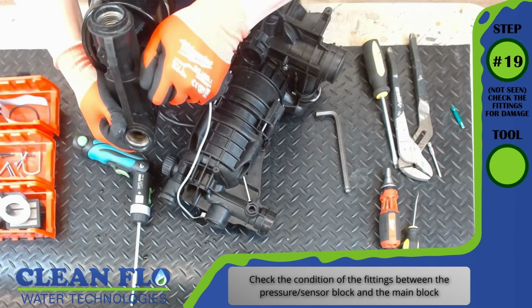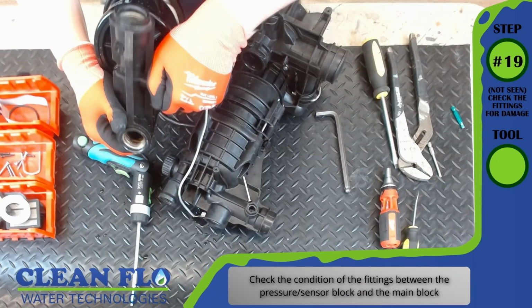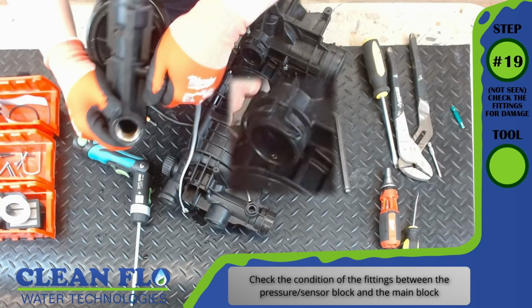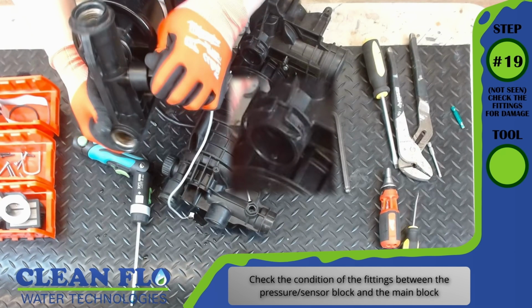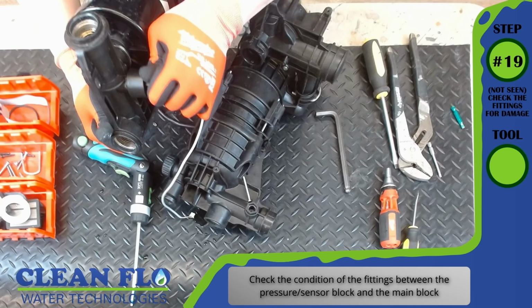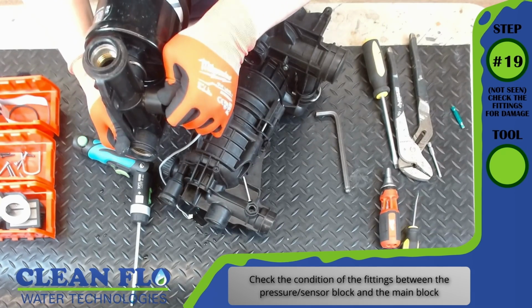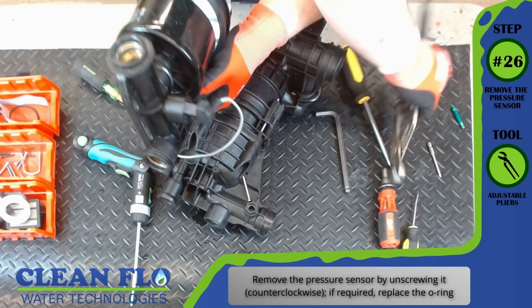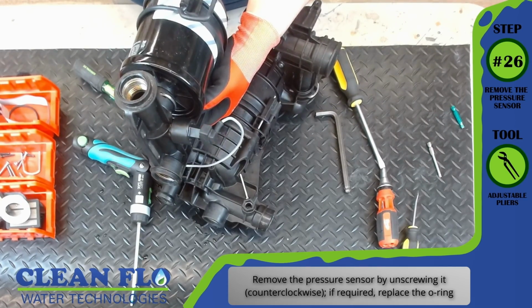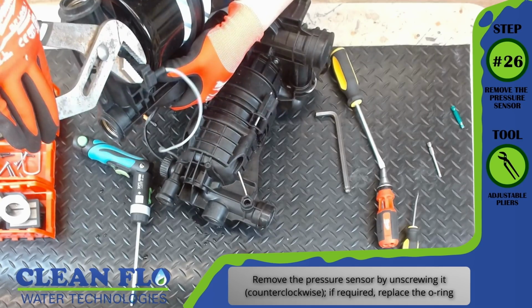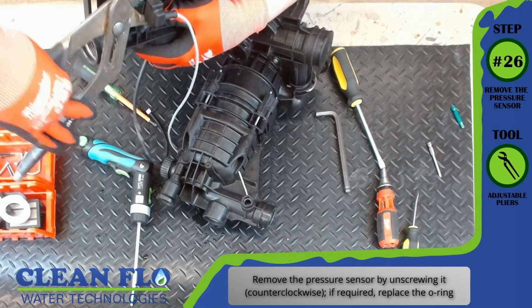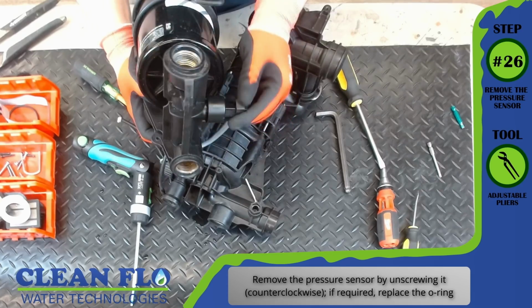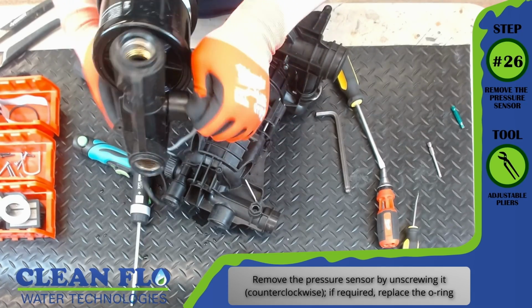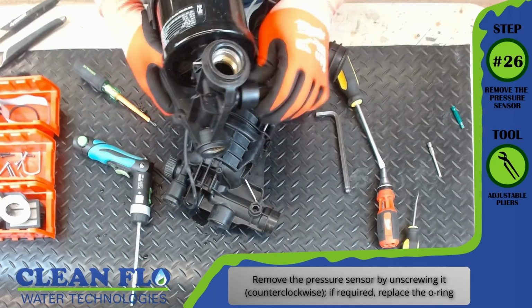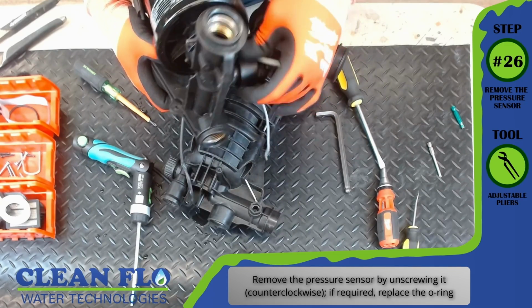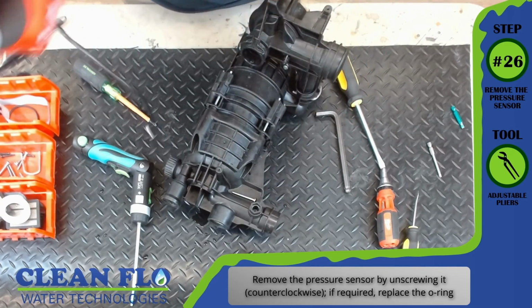Step 19, not seen. Check the fittings for damage. No tool is required. Check the condition of the fitting between the pressure sensor block and the main block. Step 26, remove the pressure sensor. Tool, adjustable pliers. Remove the pressure sensor by unscrewing it counterclockwise. If required, replace the O-ring. Please use minimal force when removing the pressure sensor. It may need the use of adjustable pliers, and when you're done, carefully store it.